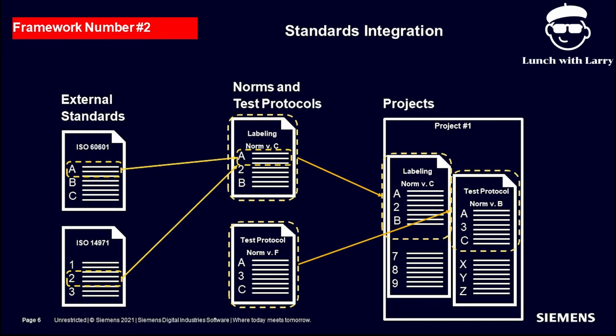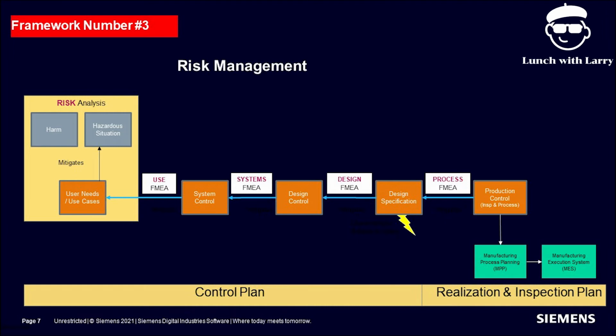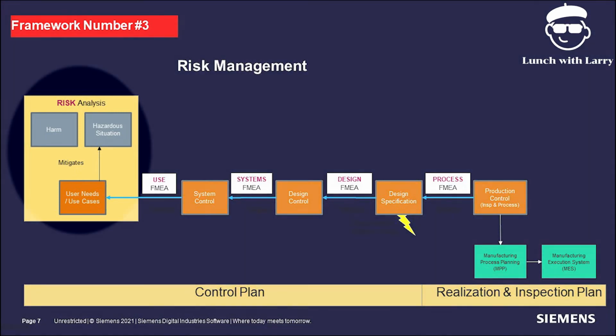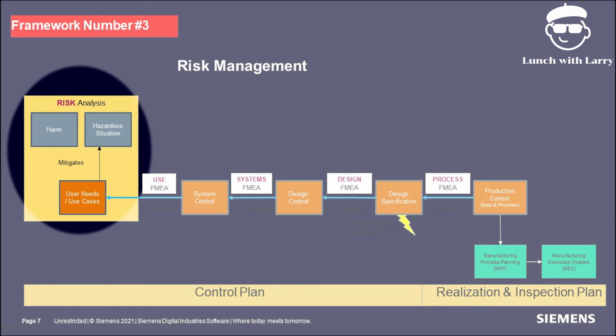Now I'm going to talk about risk management for a few minutes here, and I'm going to give you an example as we go through. Risk management is the negative view of these controls. And so the 14971 document in medical device talks about how to do a risk analysis. And this is where we're going to take harms, we're going to associate them with hazardous situations, and then we're going to create a mitigation strategy to assure that we're controlling the occurrence of the hazardous situation. So when we do this, there's a couple things that we want to get out of the analysis. The first is a residual risk analysis. After mitigation, what is the residual risk that we have associated with this particular hazardous situation harm combination? And in addition to that, we want a mitigation strategy.